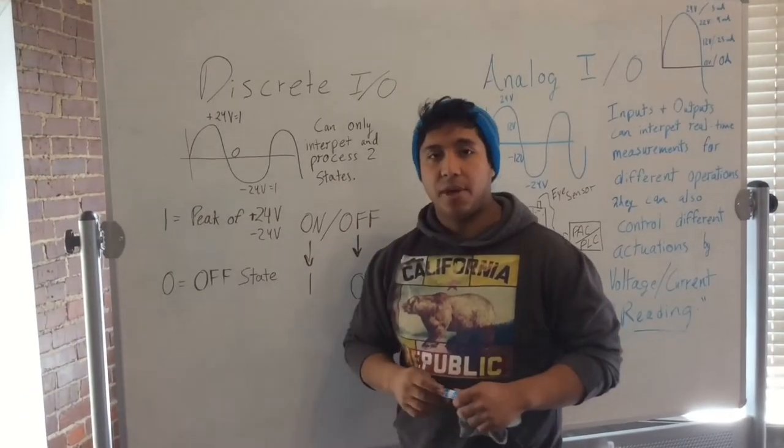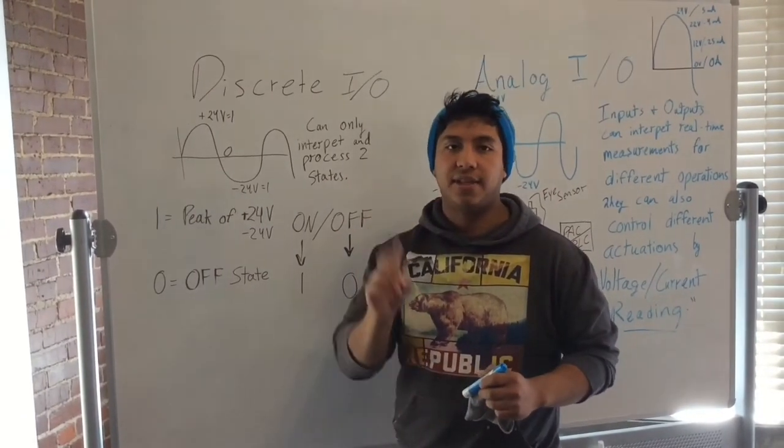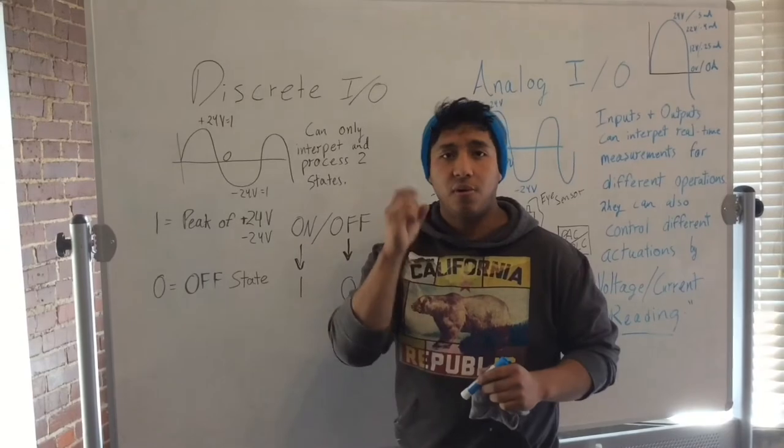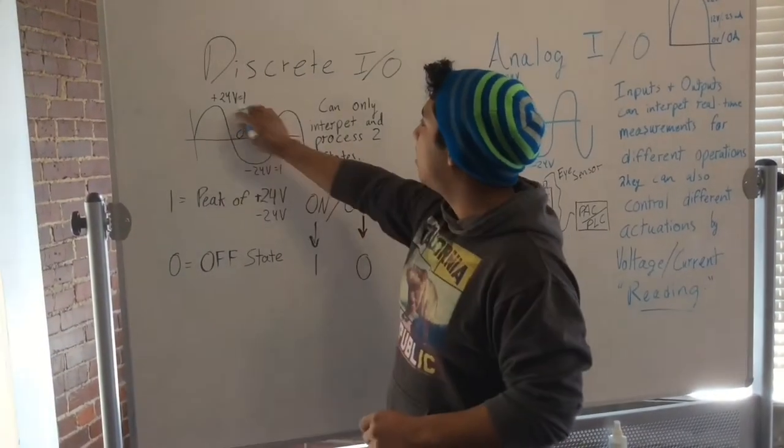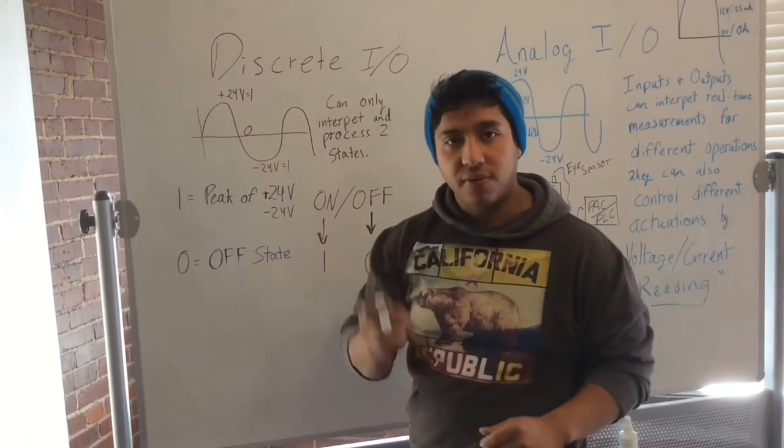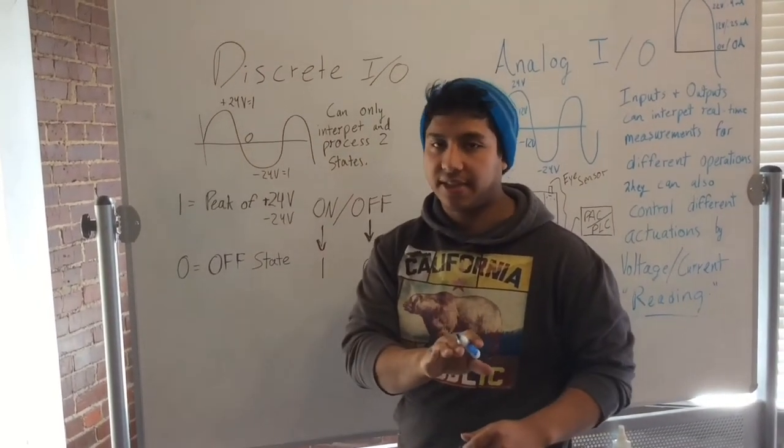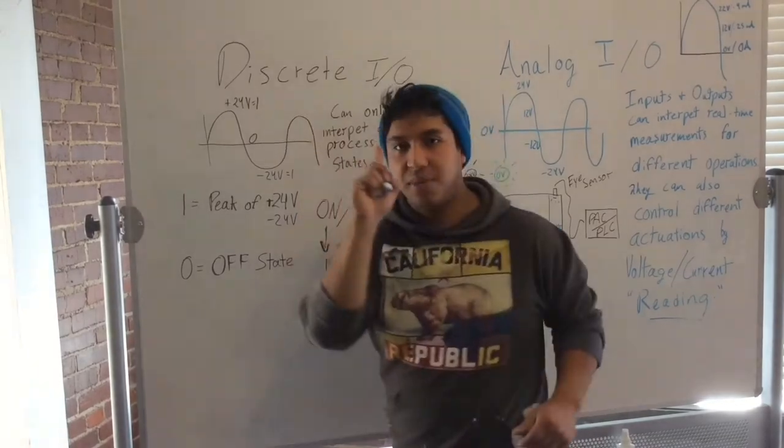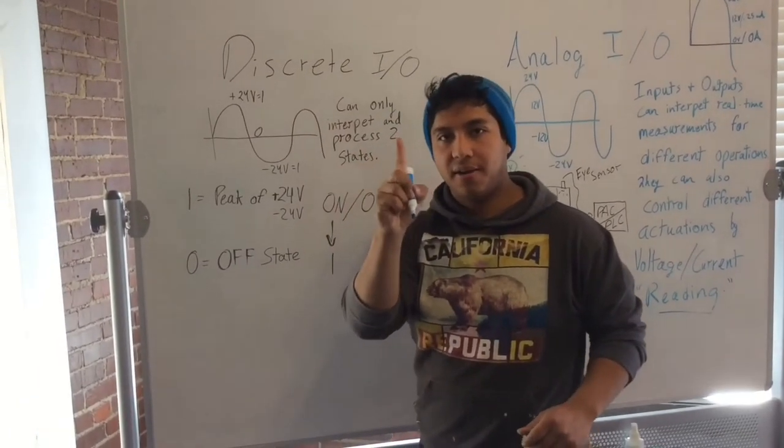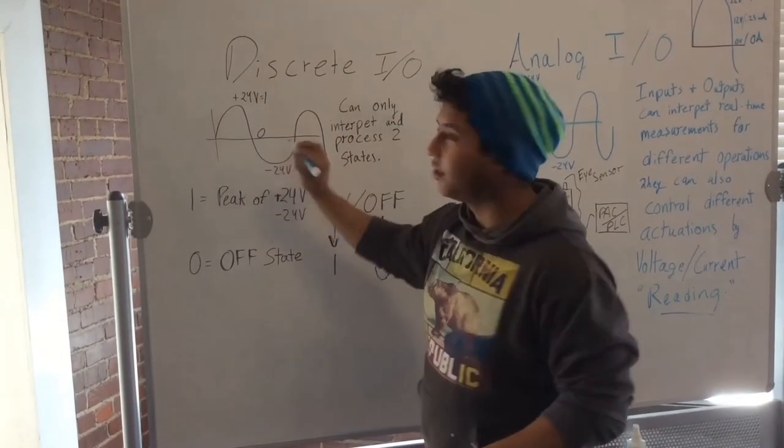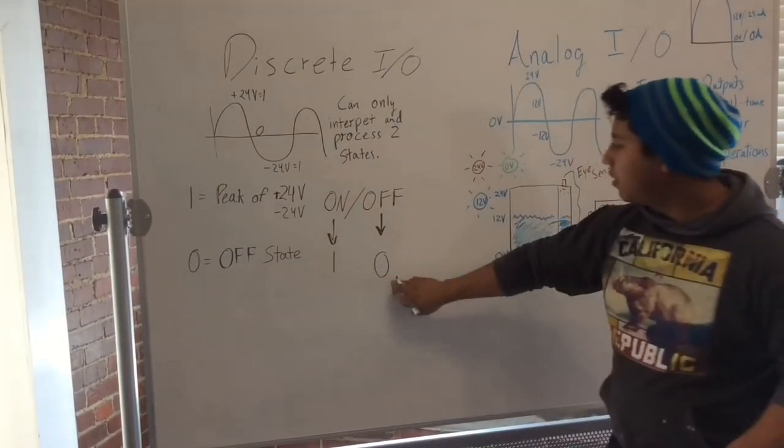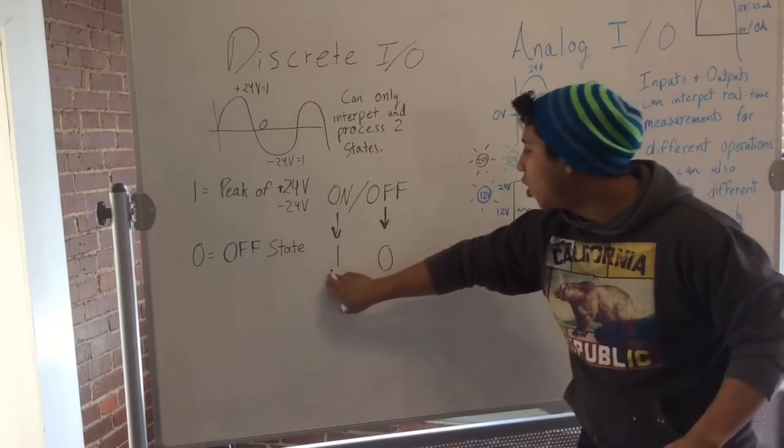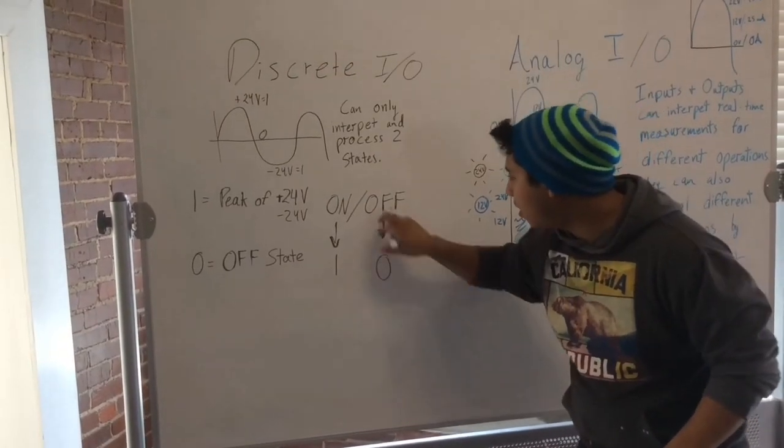The discrete input and output modules are going to only understand two states, which is zero or one, off or on. And the way that works is that once it reaches to the peak of 24 volts, I'm using that as an example, that is going to be the on state, one. But once it reaches down to zero, or the off state, that is going to be off state zero. So that's going to be your binary. One, on, zero, off.